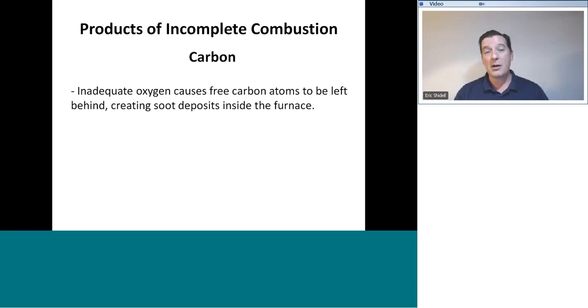If it is so starved for oxygen that free carbon atoms are being left behind, you are also going to produce an awful lot of carbon monoxide. So you know immediately you have a very dangerous burning flame. A burner should not be left alone and should not be allowed to continue operating that has evidence of carbon soot taking place. That is an extremely dangerous situation, and you definitely cannot allow that burner to continue operating.